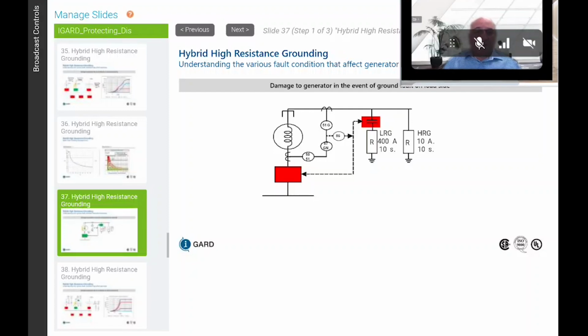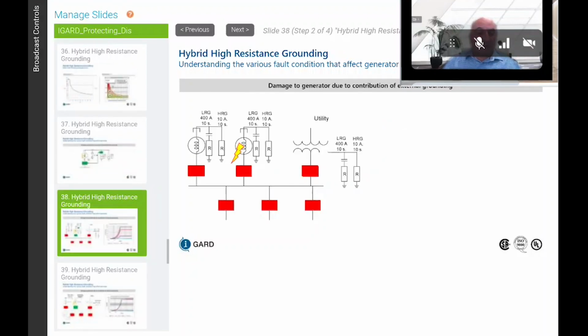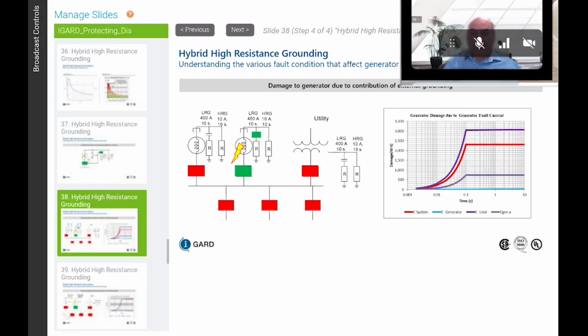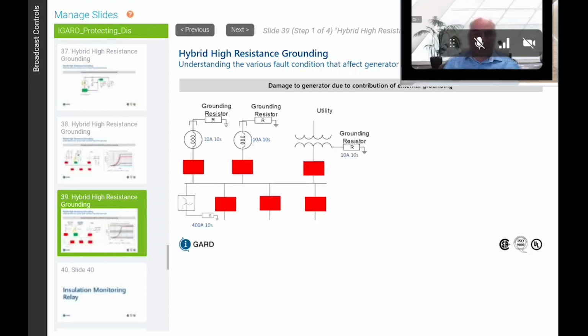So what happens is you get a ground fault. You simultaneously have a low resistance grounding system and a high resistance grounding system connected to the neutral of that generator. When you have a differential fault, the differential picks up, you open the circuit breaker for the generator, and the high resistance grounding system allows that generator to coast down with a 10 amp fault on it. So this is how it looks with a 10 amp fault on it. We've minimized the damage to 3,000 watt seconds due to the other two resistors.